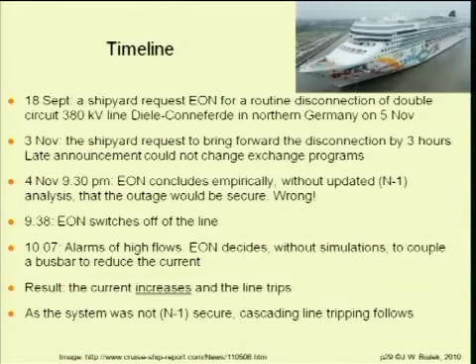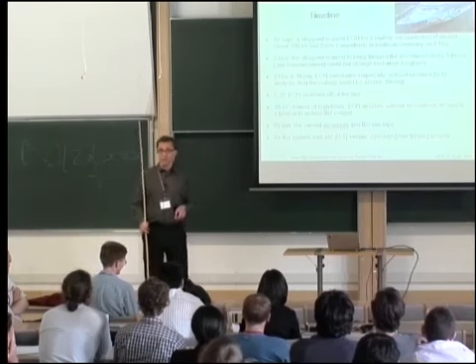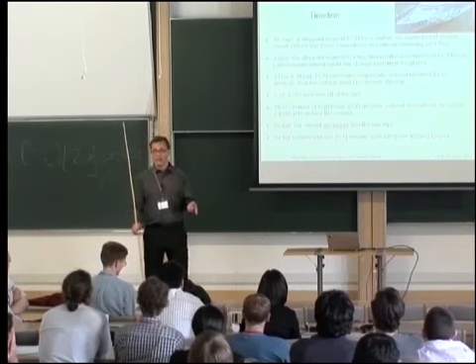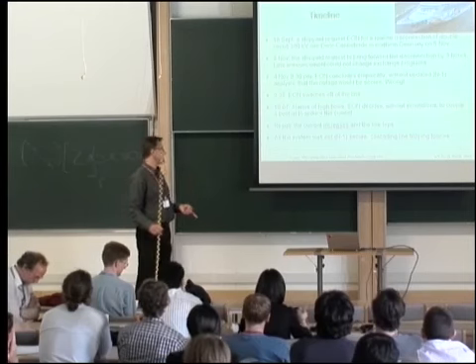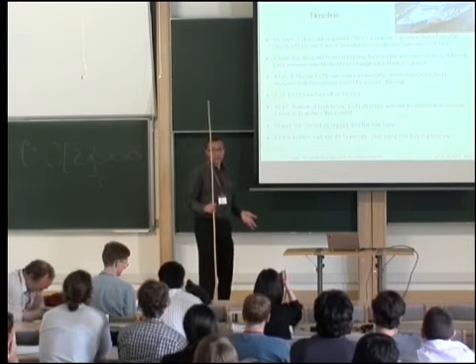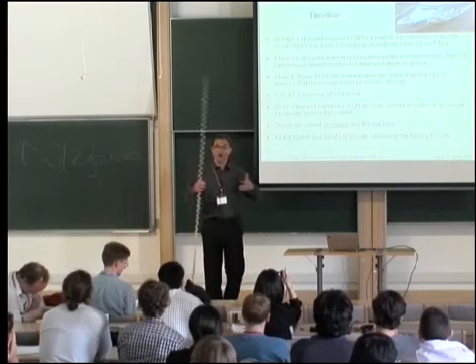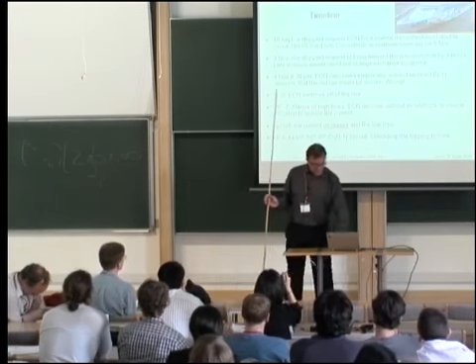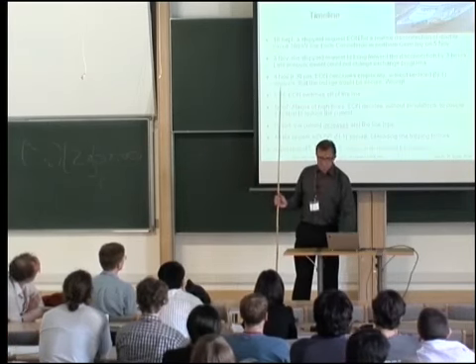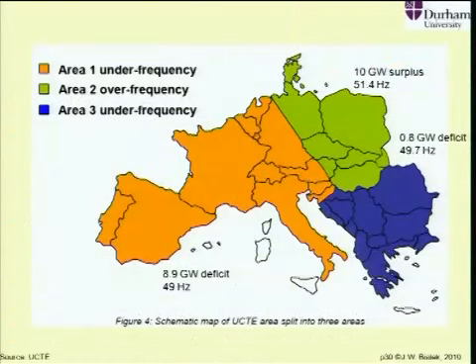And basically, because the system was not N-1 secure, because they hadn't done the proper N-1 security analysis, there was a cascading tripping. So the lines started to trip over the whole of Europe, and the UCTE was separated into 3 regions with different frequencies. So you have the western part, which was the net importer, so they had an 8.9 gigawatt deficit. So this is equivalent to about 6-7 large power stations.